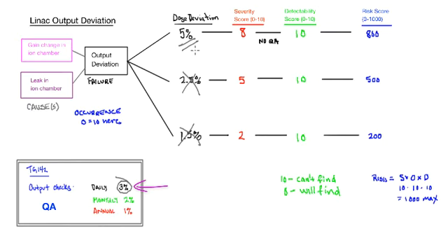So this is just a function of how sensitive this test is, how it's performed. So let's add it in now to this branch here. Instead of having no QA, we're going to do daily QA as recommended by this report. And what that's going to do is impact this detectability score. So let's say it goes down to 1 now. You're almost sure to find it.